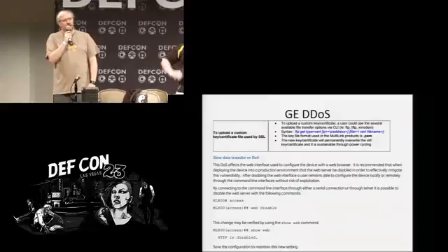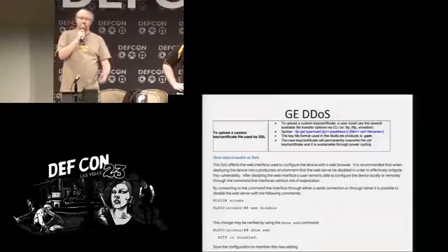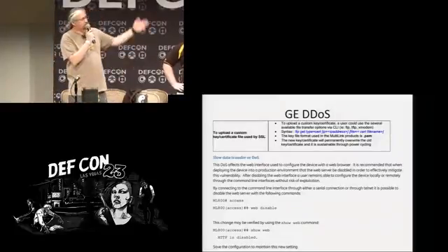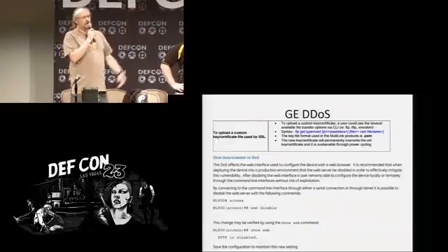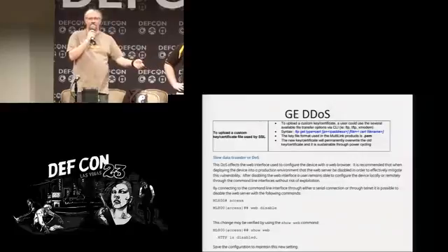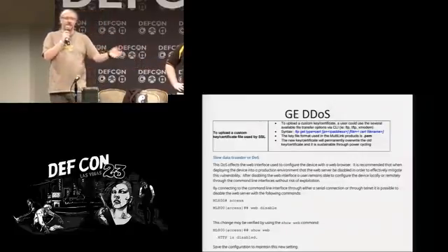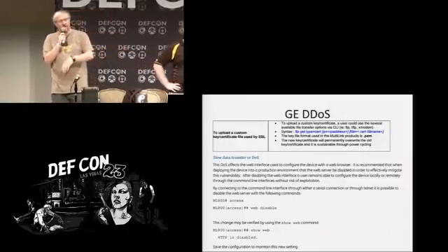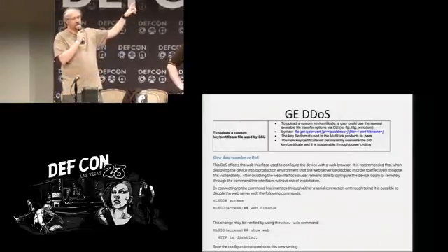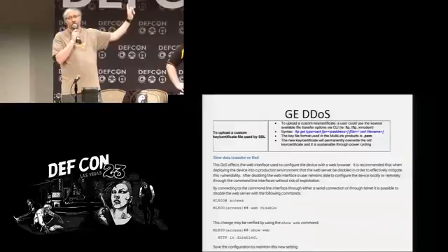But they do really matter in industrial systems, particularly when the web server going down causes the switch to reboot for 2 minutes and all the traffic to be dropped in that time period. So this is the fix, the current fix from GE. They had to go to Garrettcom and ask Garrettcom to fix it. And I think originally Garrettcom said, sorry, this is end of life, and now they've changed their mind, and now they're patching it. But I want you to read that very carefully. Their mitigation is basically turn off the web server.